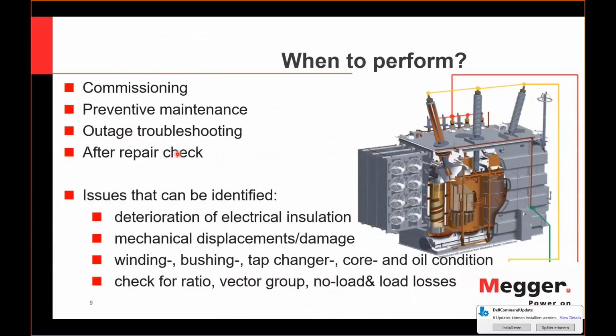So when do you perform tests on your transformer? Typically in the very beginning of the lifetime, at the stage of commissioning, when the new transformer arrives at your substation, you are doing the check. When you run the transformer for many years, it's good practice to make periodic checks, like every 4 to 5 years. You stop the operation and schedule comprehensive testing. This is done to prevent an outage in the future.